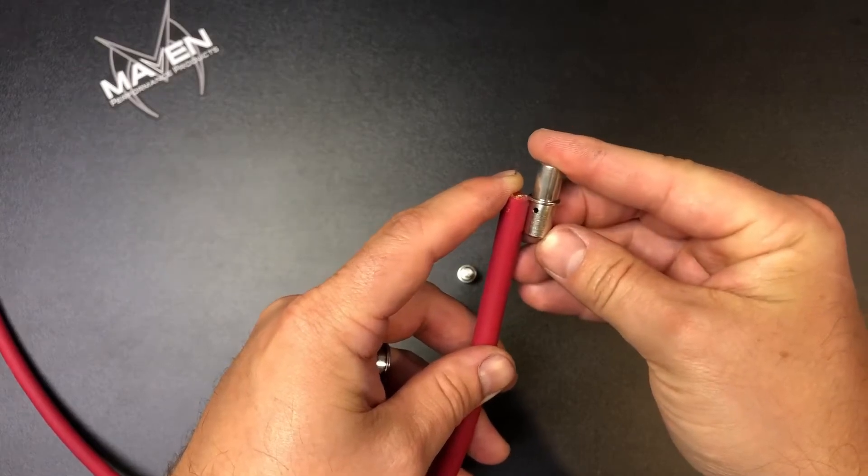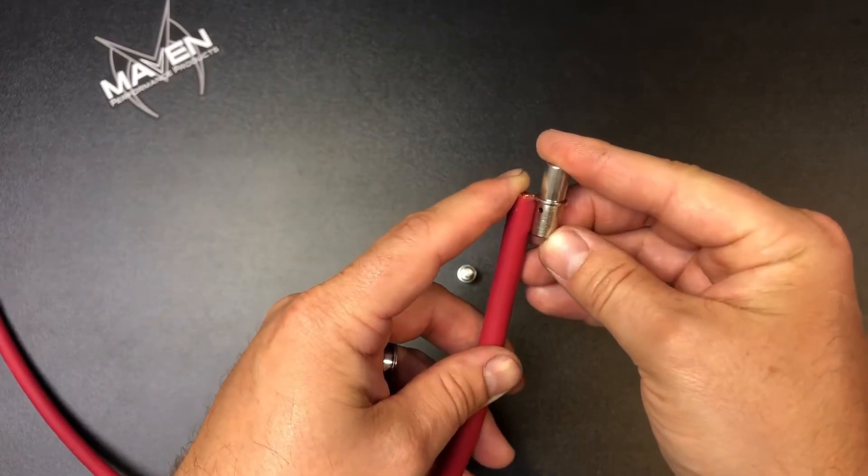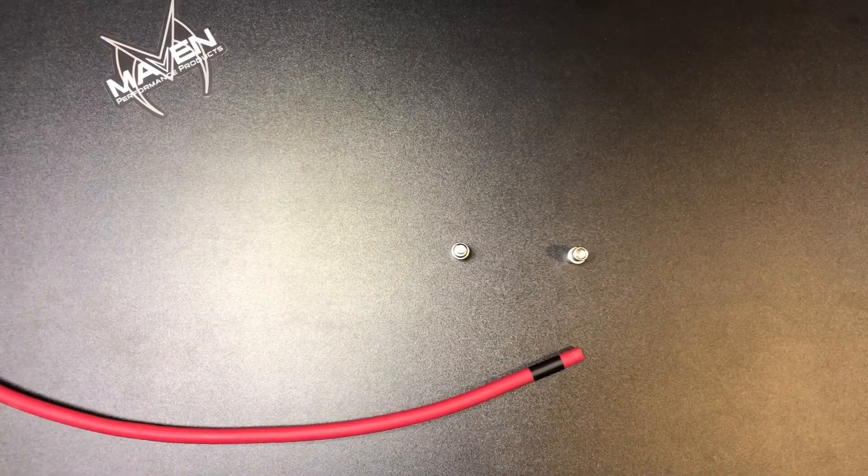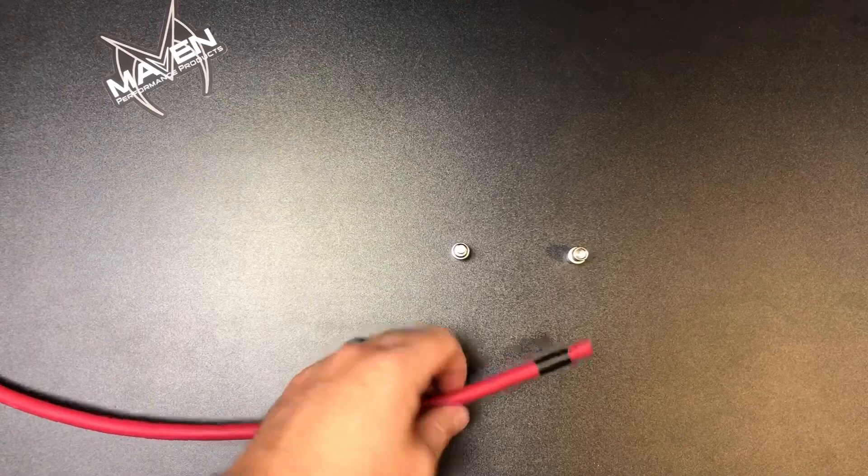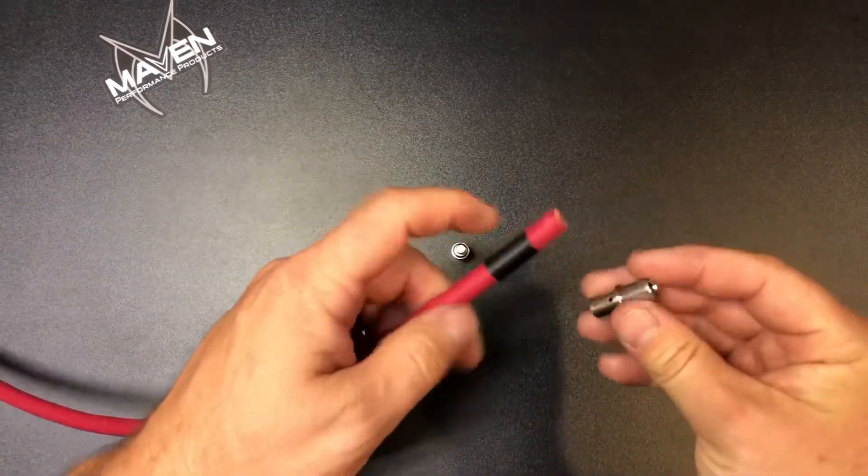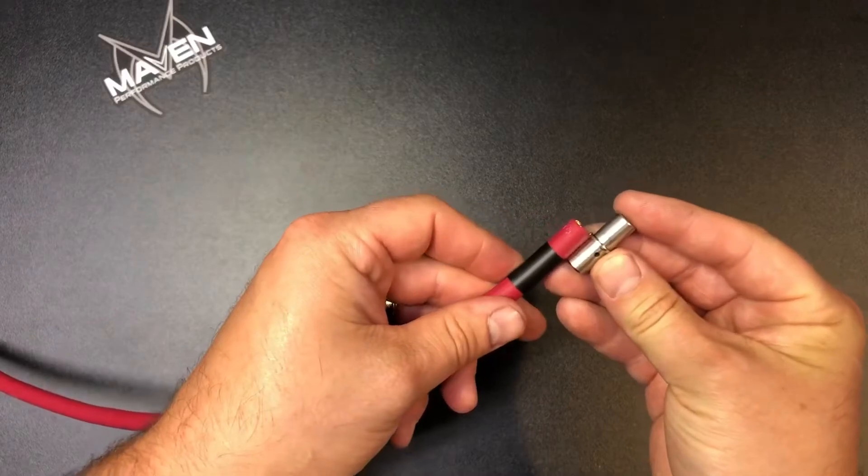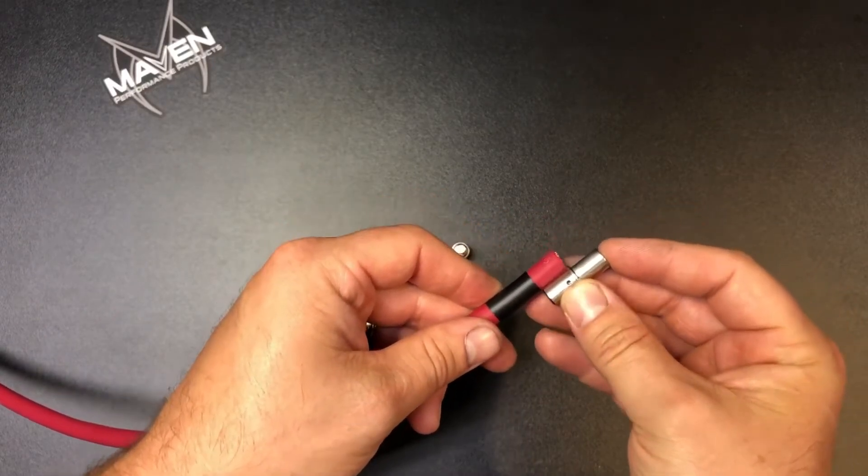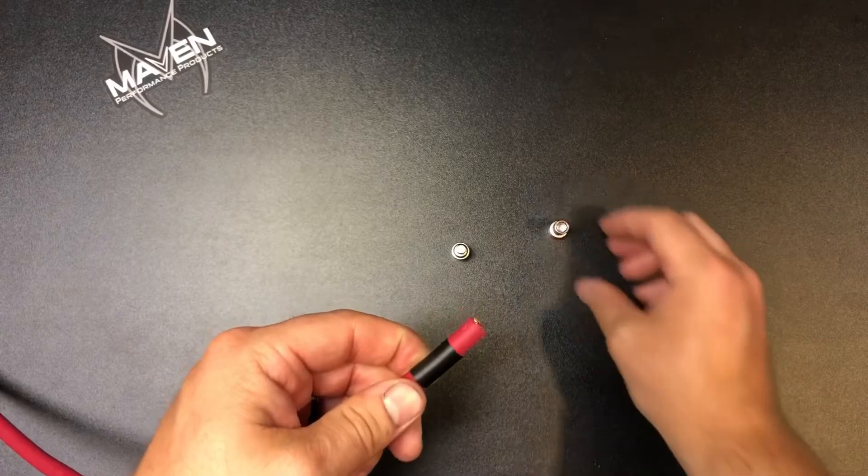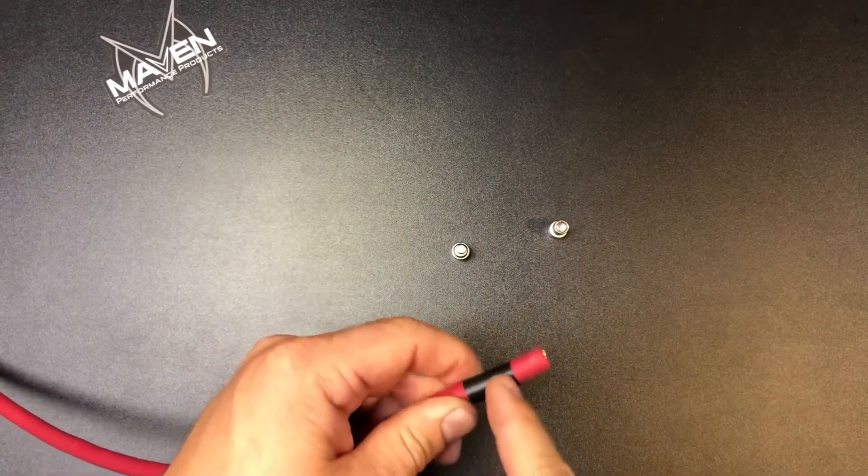One thing I like to do when stripping the insulation off this four gauge cabling is to put a piece of tape on it. I use this as my guide—the terminal—to make sure I have enough depth plus a little. Then I'll often just use a utility knife. Just make sure you're really careful when you cut through the insulation so you don't get into the wire.